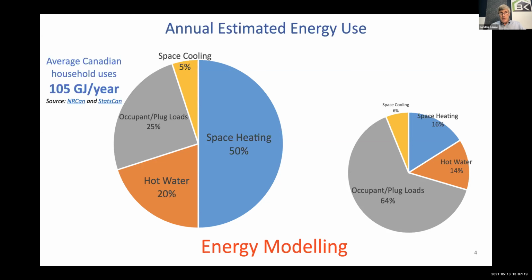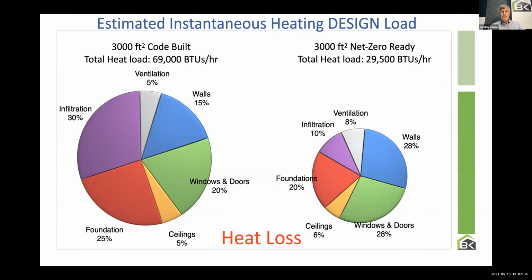It's nice to know, but what we really want to know in terms of sizing is what's happening on the design day. That is, how big does our equipment need to be? So that's where we're heading, to what equipment we need, or what size we need that equipment to be. So this is looking at the estimated instantaneous heating design load, and this would be referred to as the heat loss.